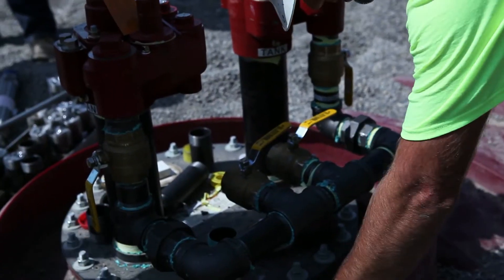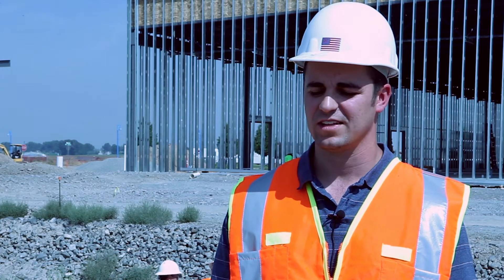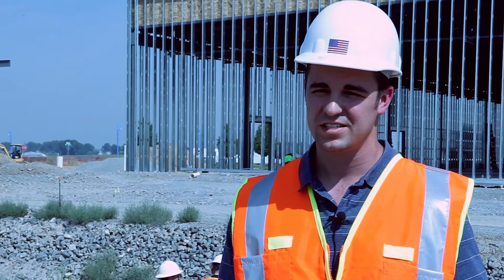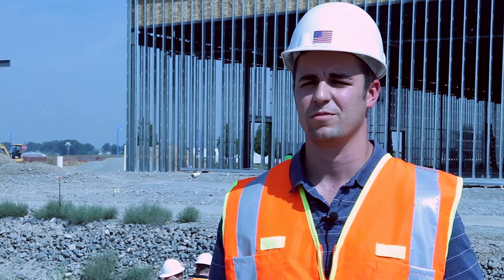When you manifold the pump configurations, if one pump dies you have the other one available. With one pump running you're not at optimal flow rates, but your site is still online — it'll hobble along during busy times, and during non-busy times you won't even notice it. The customer will still get 10 gallons per minute on the retail side or 60 gallons per minute on the commercial side with just one two-horsepower pump.